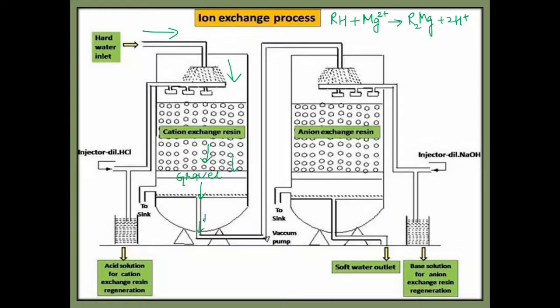The water which is having H plus as the cations and all anions still present in the water, that will come down. So your hardness, which is calcium and magnesium, is actually removed here only at the very first stage. So if you would like to say that the water is softened, yes, the water is softened here only at the very first stage. But I want to purify the water, I want to utilize the water for industrial purpose.